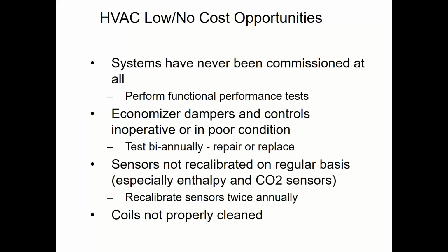But if you do it, there's a lot of benefits. For starters, if you clean the coil, there'll be less debris on the surface of the coil, and it's easier for air to move through the coil, and it will lower the pressure drop of the coil, which means it'll take less fan energy to operate. So on your indoor evaporator coil, by cleaning that coil, it'll cost you less blower energy. And the same thing on your outdoor condenser coil. All right, so you can save energy, fan energy, by having clean coils.